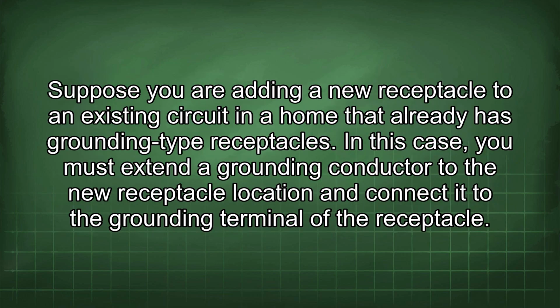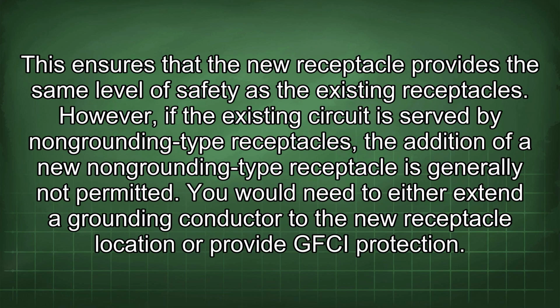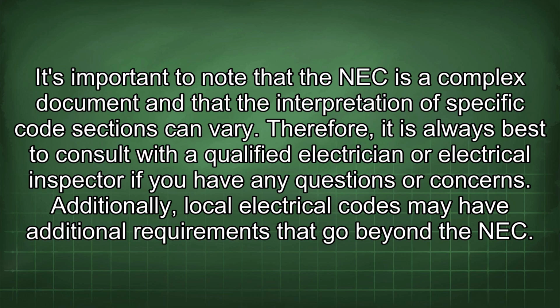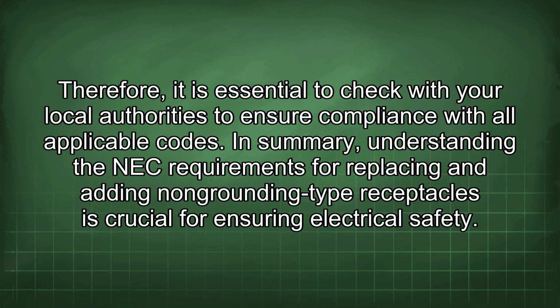Now let's consider a different scenario. Suppose you are adding a new receptacle to an existing circuit in a home that already has grounding type receptacles. In this case, you must extend a grounding conductor to the new receptacle location and connect it to the grounding terminal of the receptacle. This ensures that the new receptacle provides the same level of safety as the existing receptacles. However, if the existing circuit is served by non-grounding type receptacles, the addition of a new non-grounding type receptacle is generally not permitted. You would need to either extend a grounding conductor to the new receptacle location or provide GFCI protection. It's important to note that the NEC is a complex document and that the interpretation of specific code sections can vary. Therefore, it is always best to consult with a qualified electrician or electrical inspector if you have any questions or concerns. Additionally, local electrical codes may have additional requirements that go beyond the NEC. Therefore, it is essential to check with your local authorities to ensure compliance with all applicable codes.